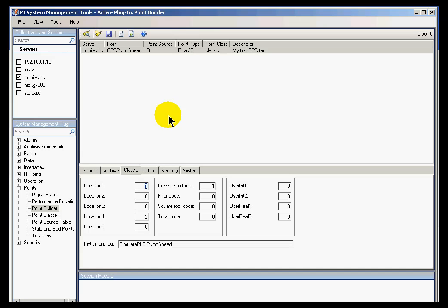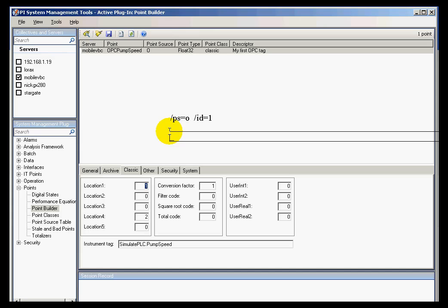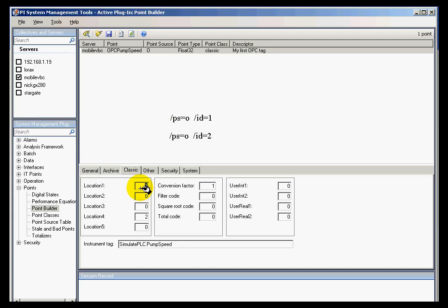In a situation like that, you may see, for example, /PS=0 followed by /ID=1 configured on one interface, and at the same time a second interface has the same point source, /PS=0 /ID=2. The function of this location code is to identify which copy of the interface we are going to be working with, interface 1 or interface 2. That number that's passed as the ID is what you put in this field right here, location code 1.